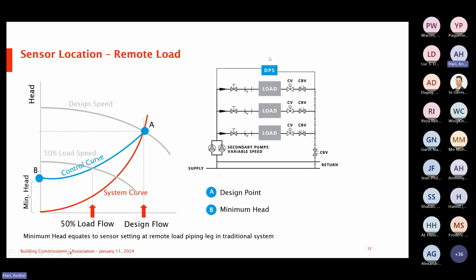When ASHRAE mandates that that DP sensor is located at the most hydraulically remote load, what that means then is that at zero flow, we only need to have the head pressure from here to here for that to be in equilibrium. The end result is that now at lower flows, we can actually drop the speed significantly more because our control curve is much more of a quadratic. And the end result is that at 50%, we're way down here and we're achieving those energy savings.